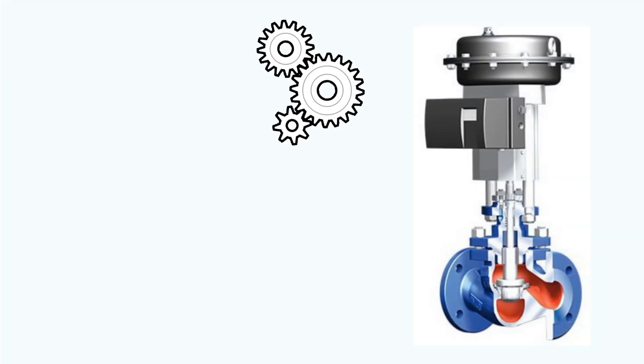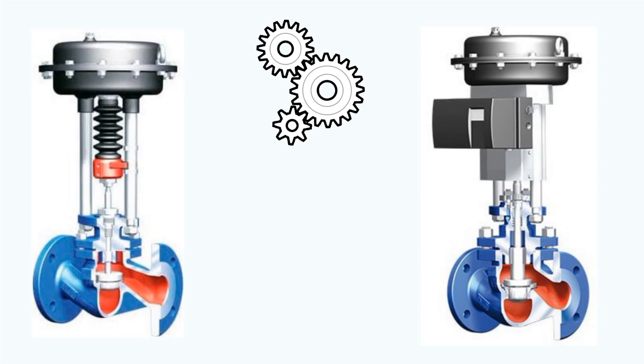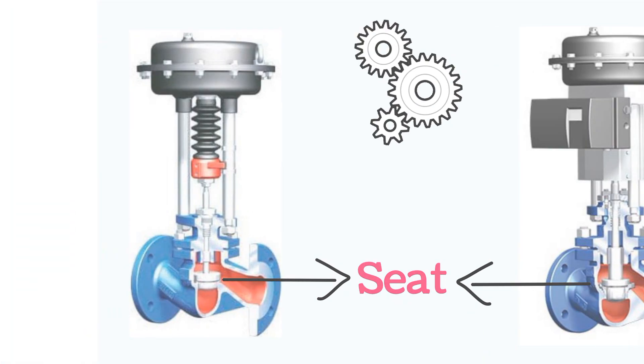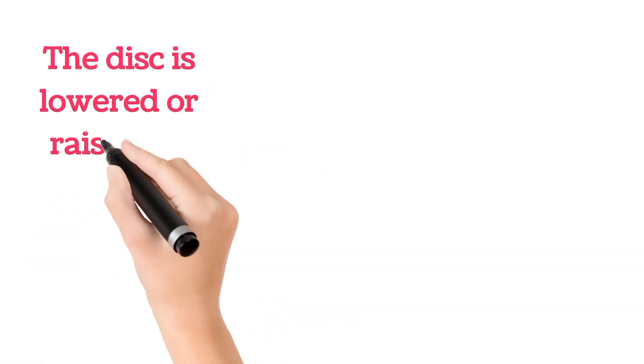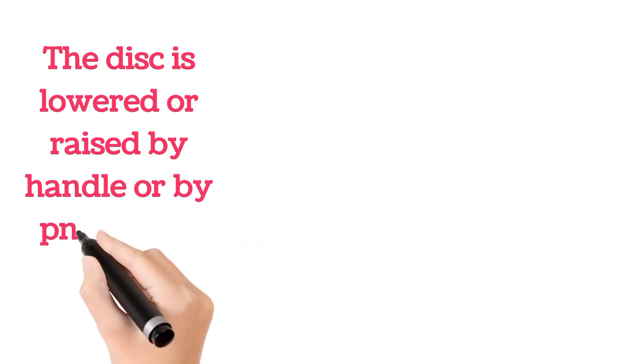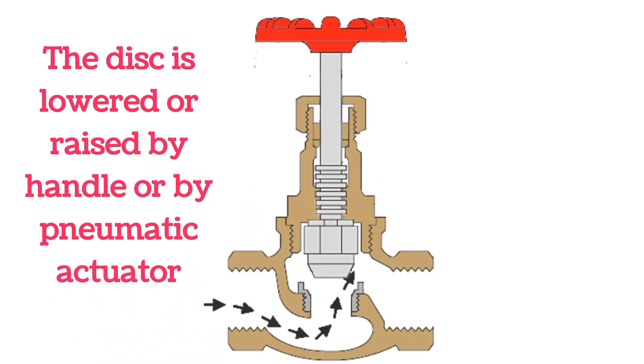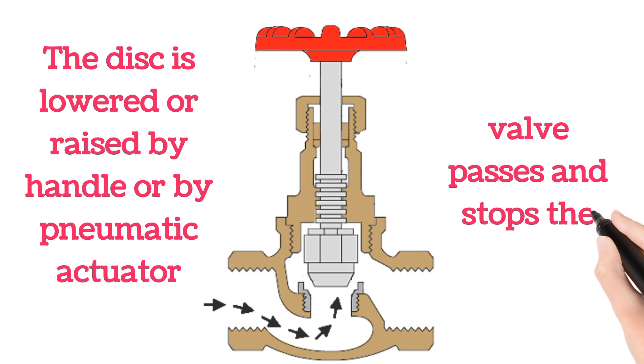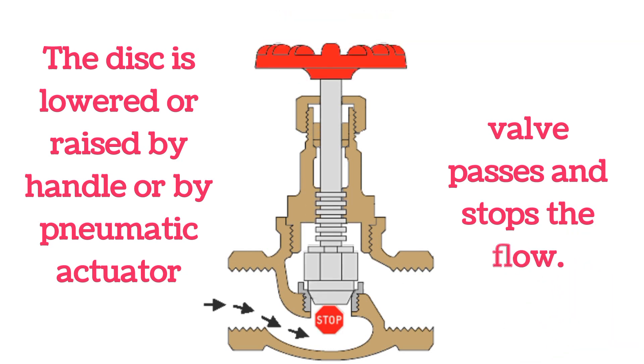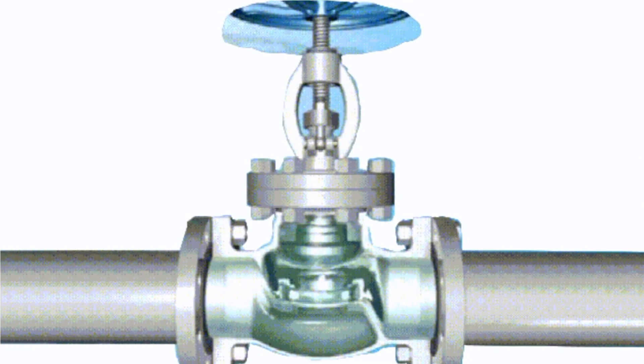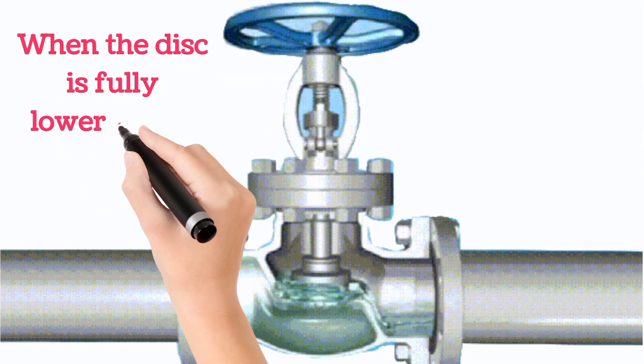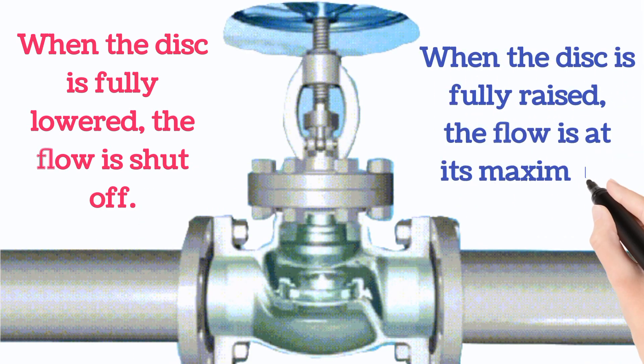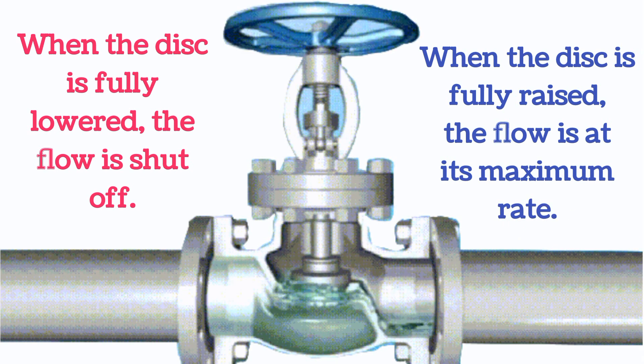Here the globe valve seat is shown in these images with the help of arrows. The disc is lowered or raised by either a handle or pneumatic actuator. The actuator for a globe valve is a pneumatic positioner or electro-pneumatic positioner. The globe valve passes or stops the flow by the movement of the disc. When the disc is fully lowered, the flow is shut off. When the disc is fully raised, the flow passes at its maximum rate.